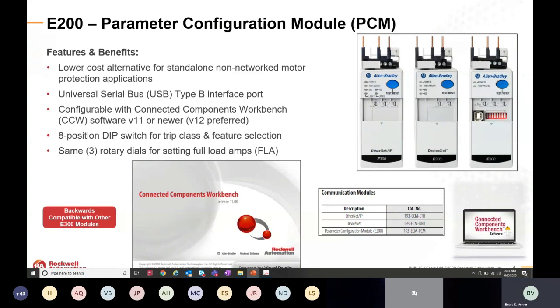If you're not looking to configure the device with a computer or CCW, it can also be configured locally from the front of the device itself. You have 3 rotary dials used to set the full load amps of the overload, and an 8 position dip switch for trip class and feature selection, so you can enable or disable things there. Again, no need to use software or a computer—you can do it all from the front of the device itself. You can see some images there from Connected Components Workbench.